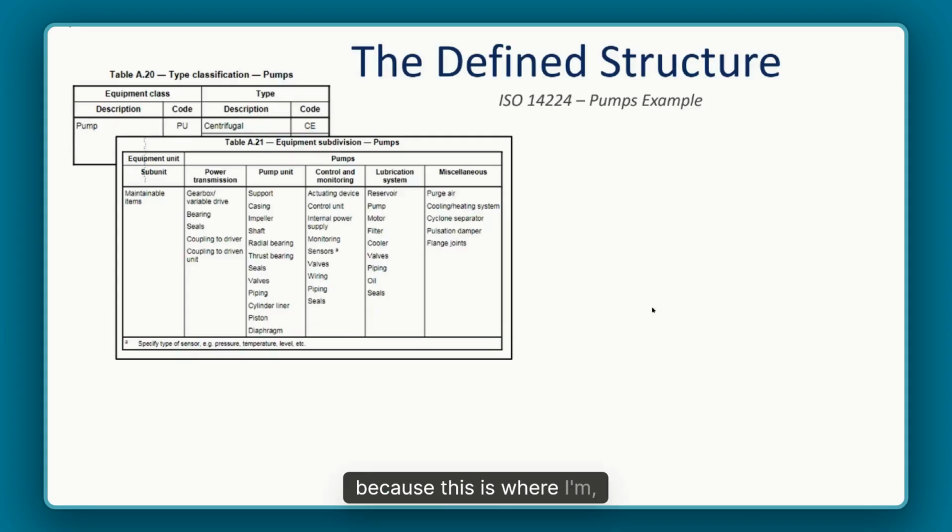Exactly, this is where I'm saying building BOMs. If people are creating work orders from a BOM, they're going to get the same material every time, because then you can quickly eliminate whether it's the purchasing, the manufacturer, or the material I'm putting in. If there are no BOMs, you've got people searching. You could have three different impellers because of cataloging duplicates or free texting. And so your variables just exploded in terms of, what's been the problem? Well, I can't tell you if it's the impeller because I don't know what was put in the last three times. Exactly.